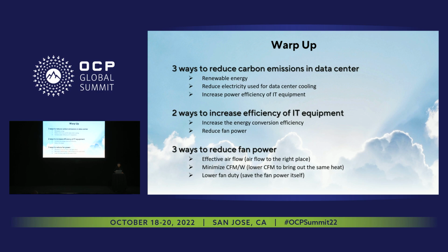There are 3 ways to reduce the fan power. Make sure the effective airflow goes to the right place to dispatch the heat. The second is to minimize the CFM per watt; the lower, the better. And the third one is to lower the fan duty, which means less power is needed to run the fan to achieve the thermal condition. So that wraps up the overall slides I have.